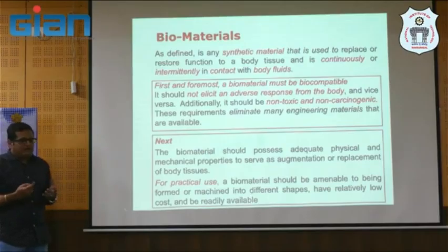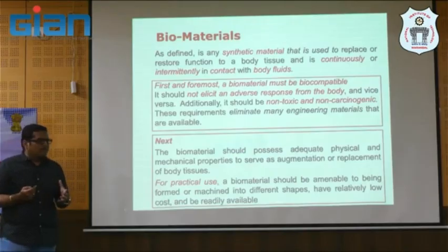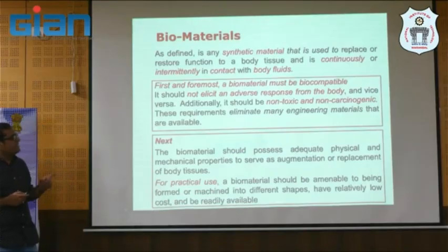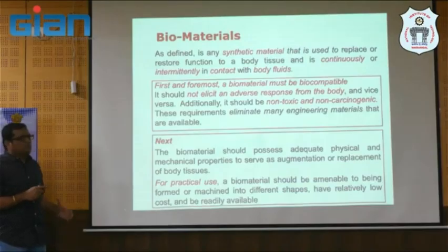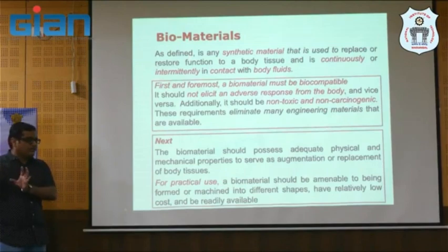So that's where it becomes very tough. Not all engineering materials are qualified. Why? Because it may be continuously or intermittently in contact with body fluid, and you are trying to replace or restore a particular function of a particular body part or tissue, whatever it is. First and foremost, it should be a biocompatible material.